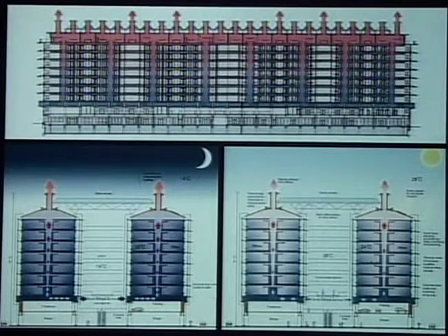The fans are blowing air from the bottom through the building to the top. So you get stack effect helping the fans. And the fans simply blow night cool air through the building and cool down the whole structure. And the way that the air runs is up the middle of the building in this duct, it goes up and connects to each floor. Each floor is a sort of heat exchange.